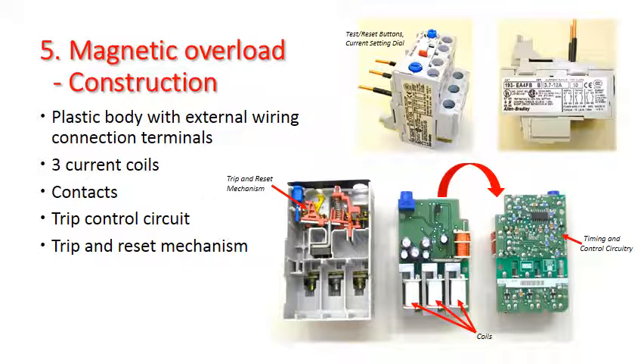Here we have a magnetic overload, and we'll look at its construction. It's got a plastic case on the outside, obviously, and terminals to connect wiring to it, and it has also terminals and prongs to connect the three phases for the motor supply to a contactor. The overload itself doesn't switch the motor on and off, it controls the contactor, which in turn switches the motor on and off. It has three current coils, as you can see in the bottom middle there. It has control contacts on the bottom left, trip control circuitry on the right, and trip and reset mechanism in the top of the overload.